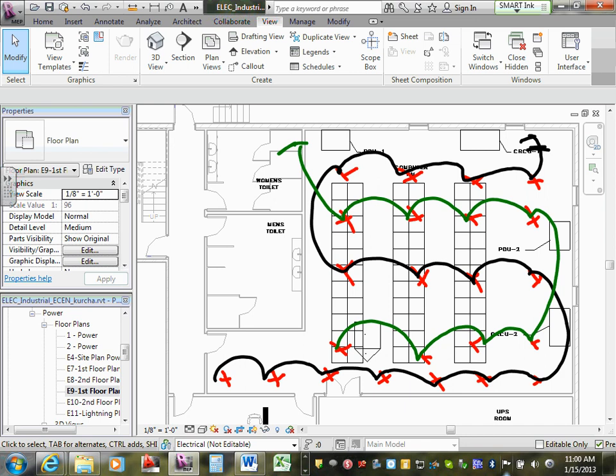Is there any limitation on how many detectors you can have on this? Depends on how big of a system. Like the NFS 640, you can have up to 159 detectors on one. And if you need more, you just throw in another loop for it. But then also you factor in the 80% of the circuit, so you're about 130. Remember, it's really not a whole issue. This is a personal system. Yeah, it's all addressable, each point. You're taking two wire signals, and like your laptop, you have an address for it.